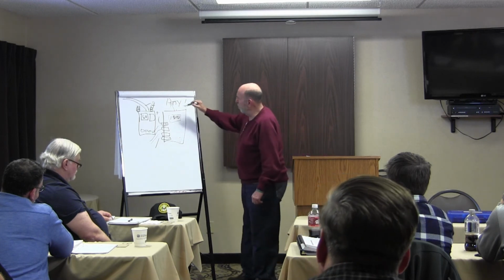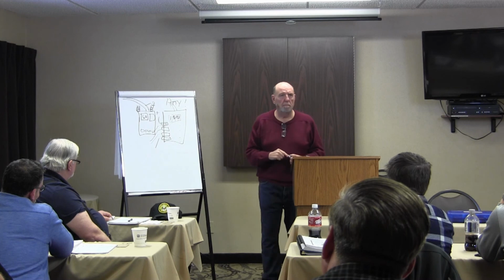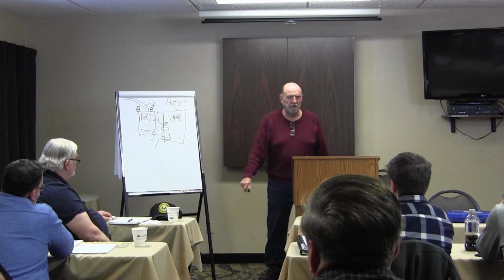Somehow the number and the formula that they use will declare whether this main wire is safe or not, even when there is no main breaker. But no, to answer your question, that number always, typically, is higher than whatever this number is. Because very seldom is every circuit going to be working at its full capacity. You've got 4 bedroom circuits that have a 15-amp breaker, unless they're having coffee pots in each room, they're not going to break.